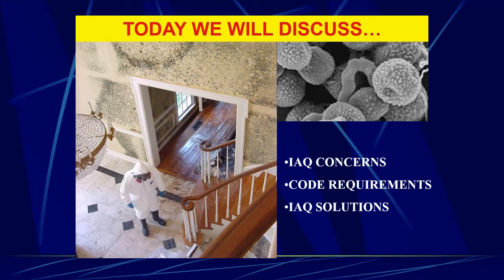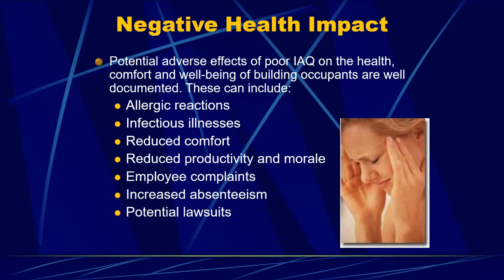Fresh outside air is used to prevent buildings from growing things inside the walls and the air ducts, things that have been proven to be the root cause of systemic health issues with the building's occupants. With no outside air or little outside air, buildings can get sick and make the people working in them sick too. The air inside commercial buildings should never be detrimental to the health of the building's occupants. The negative health impacts of poor indoor air quality are well documented: allergic reaction, infectious illnesses, reduced comfort, reduced productivity and employee morale, complaints, absenteeism, and potential lawsuits.